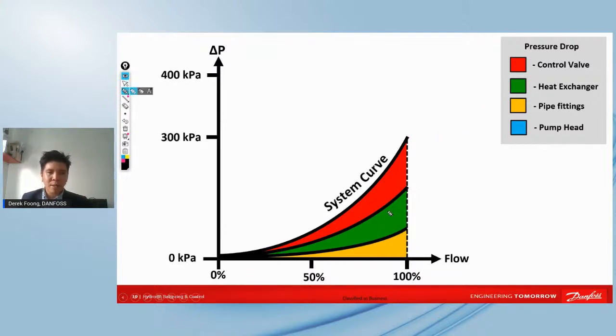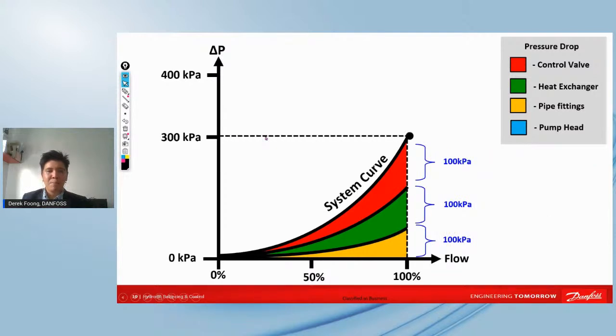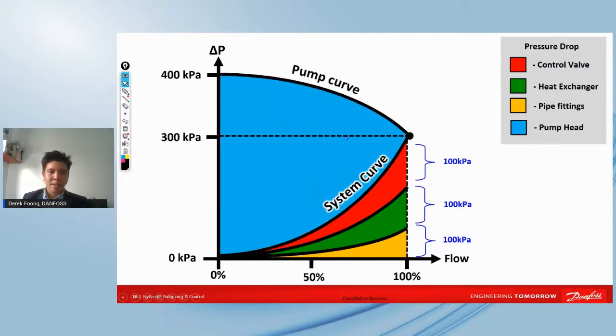And the final system curve, let's say the yellow part, we always say, okay, that's the pipe and fittings. Then you have coils, or we call them heat exchangers, at design flow, each of which has its own pressure drop. And finally, when you put all this together, you have the system curve. And this is where you select your pump, right? This is when you select the pump with all the pressures gathered together.